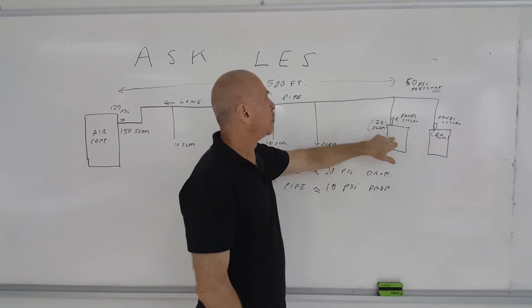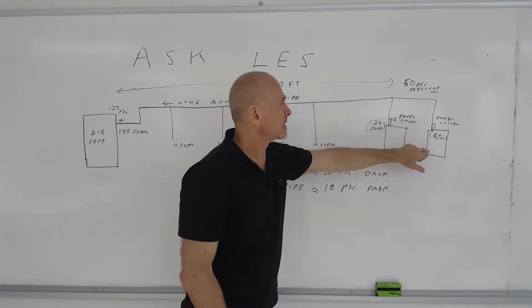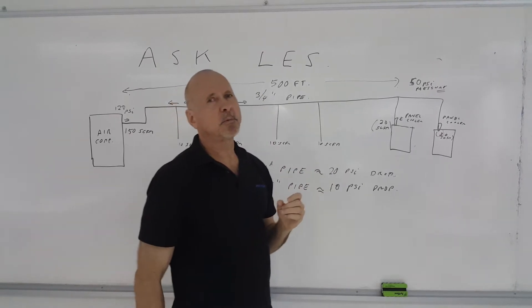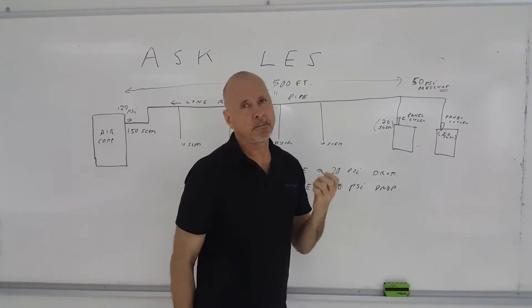So, they could get no more than about 70 pounds pressure going into those coolers. Didn't work to optimum efficiency. They needed to have 80 PSI.